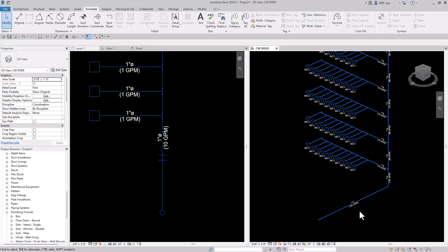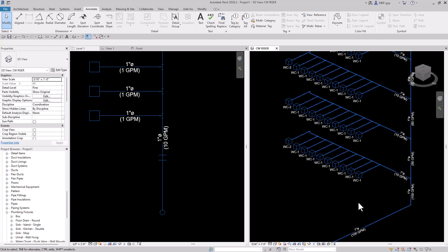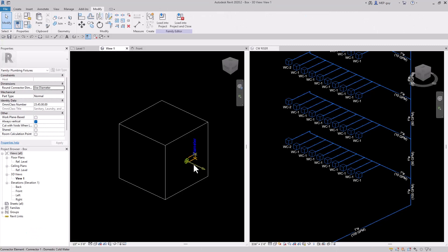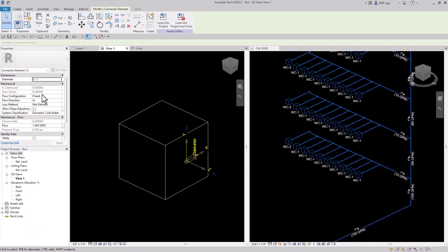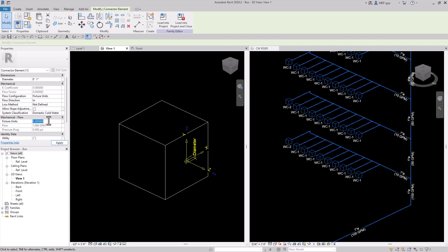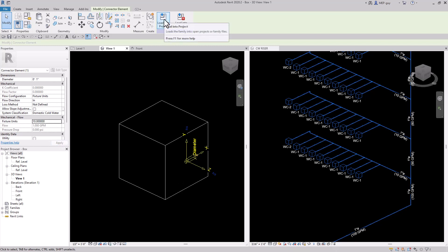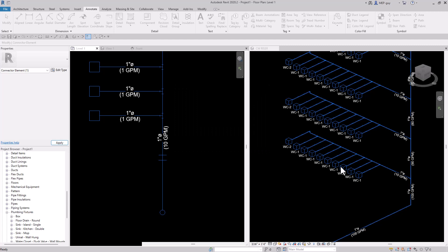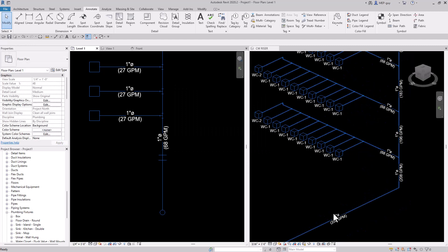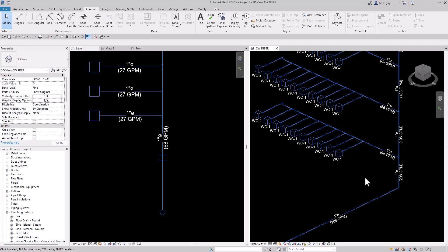A water closet is not one GPM, so we need to update our pipe connector. Let's go back into our family, click on our pipe connector, and update that from preset to fixture units. For a water closet we need 10 fixture units per water closet. We'll load it back into our project, overwrite the existing version, and now you can see all of the GPMs have updated using the fixture units to calculate the GPM.